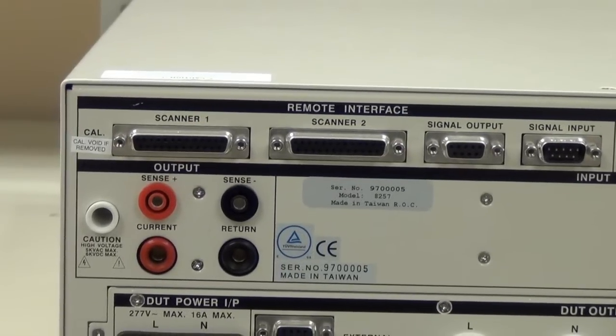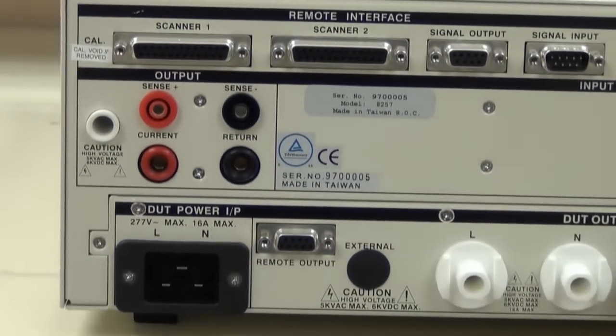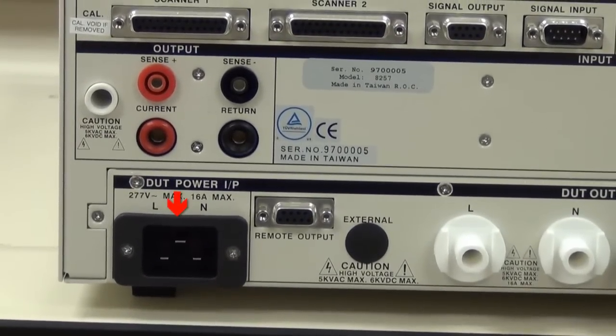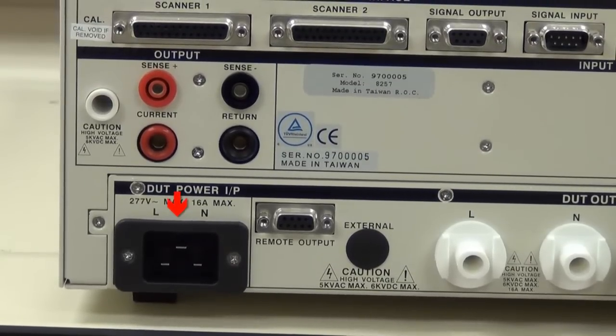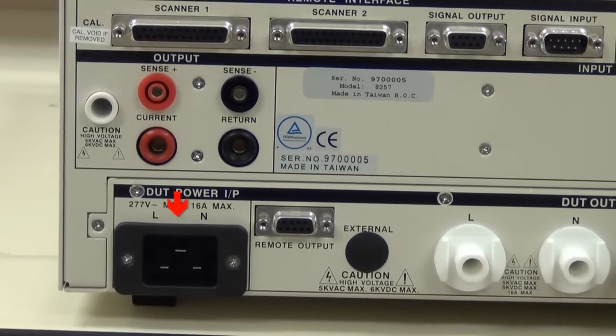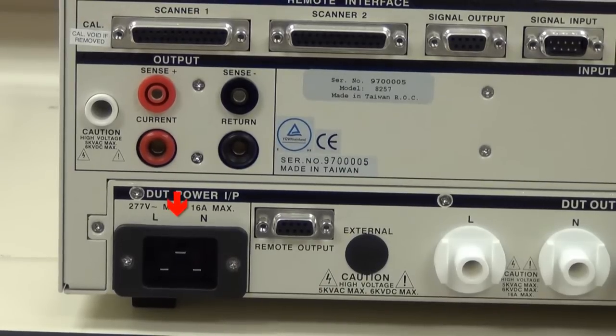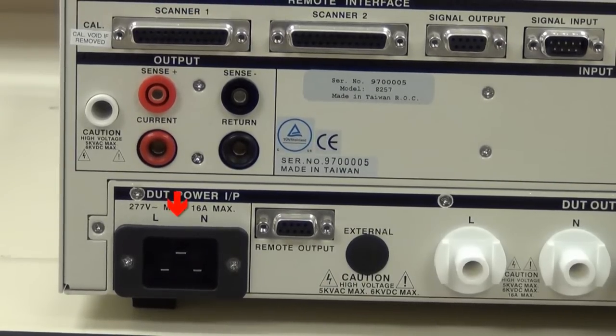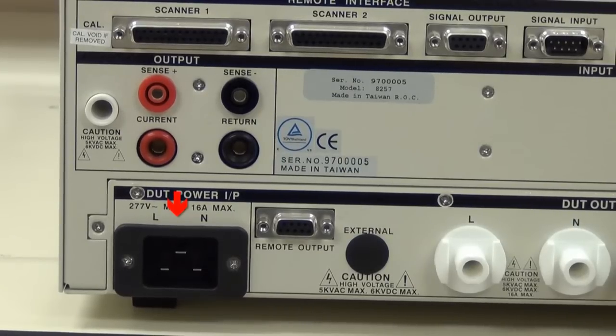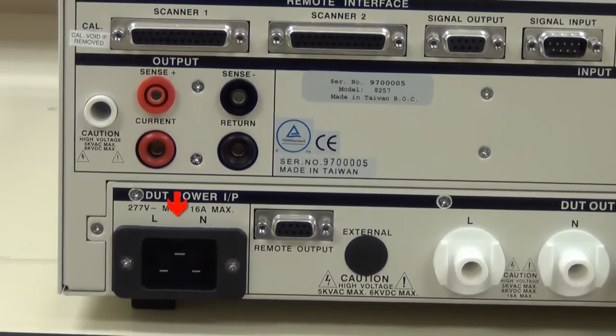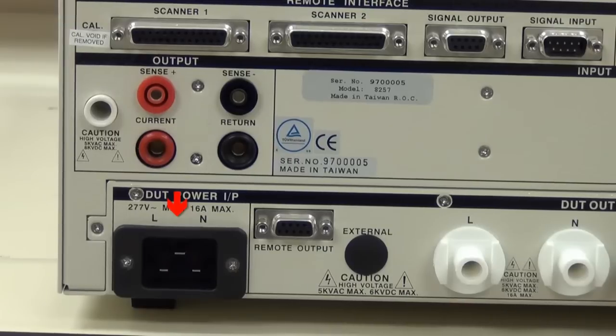The DUT power input connector provides the line and neutral input power connections on pins 1 and 2 respectively. An external single-phase unbalanced AC power supply with a single hot and neutral conductor should be connected here to supply power to the DUT while performing line leakage and functional run testing. The input is rated from 0 to 277 volts AC at 50 to 60 Hz.